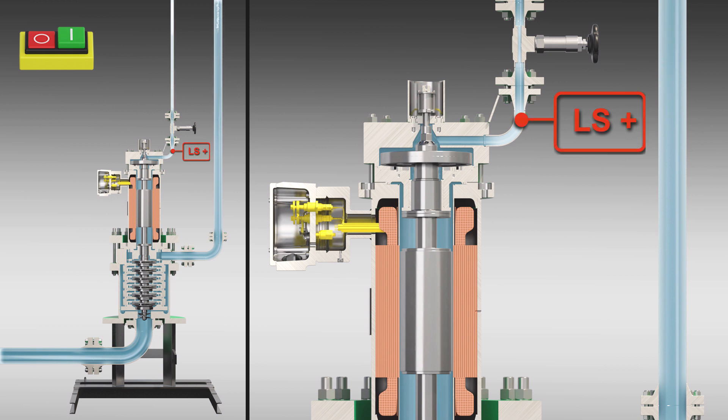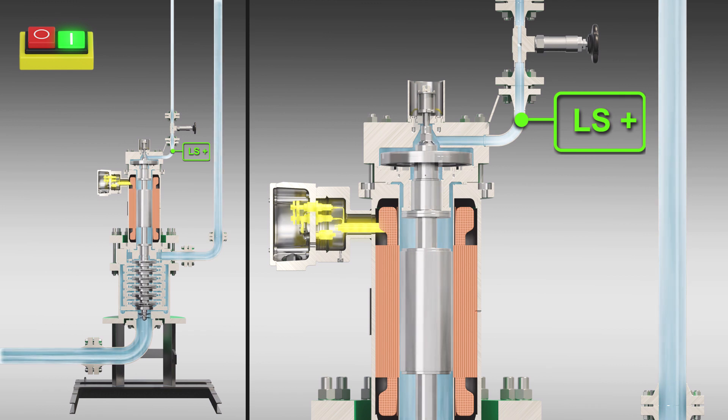The canned motor accelerates to operating speed in a matter of seconds. The partial flow is branched off at the impeller in the high-pressure range and serves to cool the motor and lubricate the slide bearings.